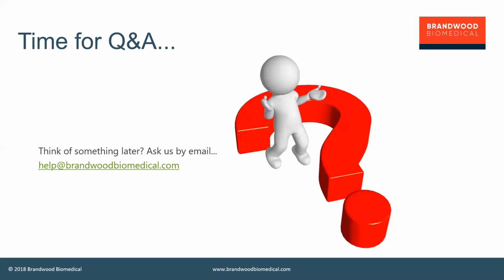I have another question here from Stephen. Stephen wants to talk about sterilization and asks, can we just expand a bit on how you might validate the sterilization using a worst case and how that works. So just want to go back and touch on that again. Okay, so sterility validation, typically the way it's done, and I'm not an expert microbiologist by any means, is that you will take your worst case sample. In here, we're talking about maybe the largest, most porous, most convoluted sample that you might ever make.